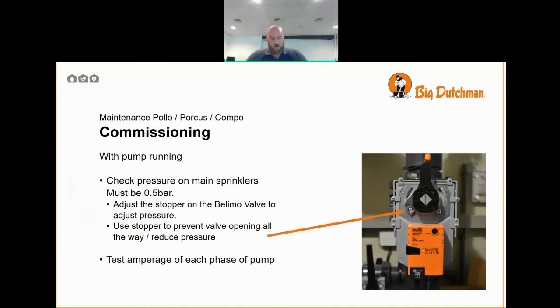Now that we've got the system running, we want to check the pressure on the main sprinklers is half a bar, or 0.5 bar. We will adjust the stopper on the Belimo valve to only allow the valve to open to a certain amount.